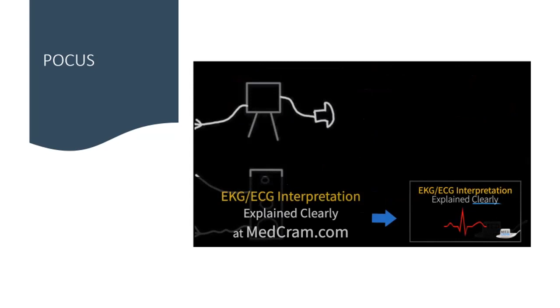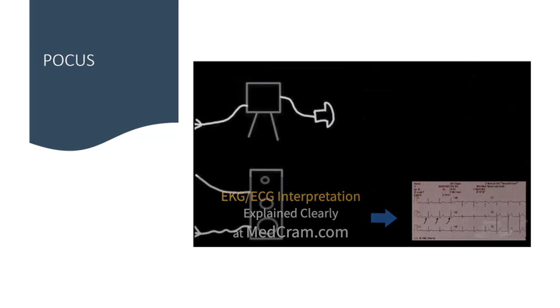Before we dive into ultrasound physics, I want to briefly explain how an ultrasound machine works. And while you may not be familiar with an ultrasound machine, you're likely familiar with the speaker. And since they both generate sound waves, it provides a good example. The speaker uses electrical energy, and the electrical waves that travel through the speaker cable cause the speaker to pump in and out. This generates sound waves in the air, which are then heard by the human ear. Well, similarly, the ultrasound machine uses electrical energy. The electrical waves generated by the ultrasound machine travel down the transducer cable into the transducer, and the transducer produces sound waves.